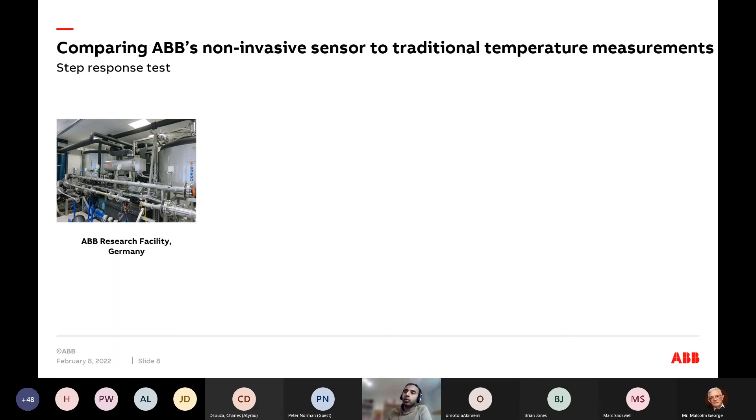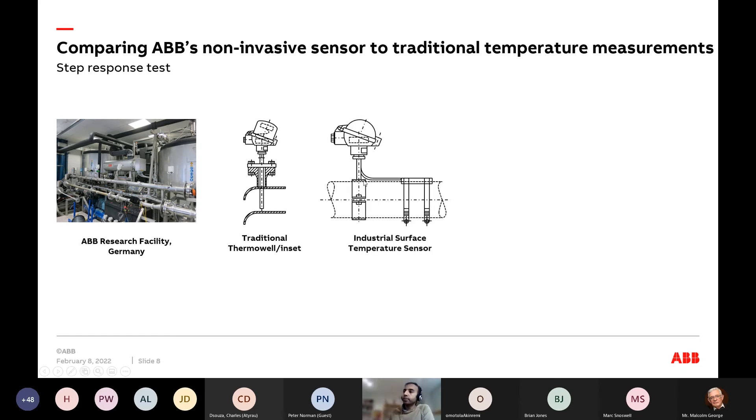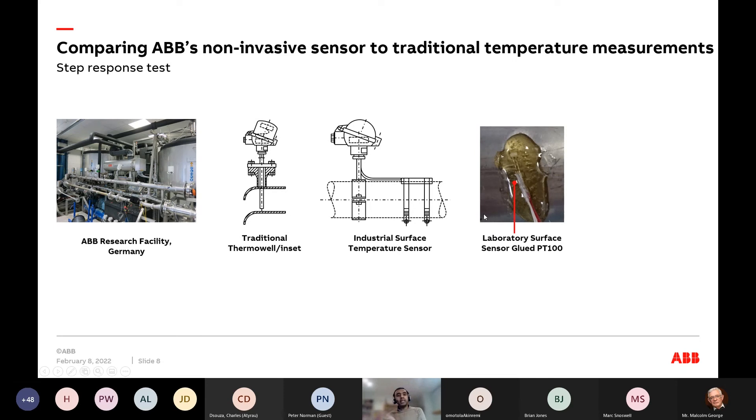Let me show you how this physics plays out in real life. This is our research facility in Germany — two tanks where we heat up water and pump it from one tank to another through a metal pipe. We compare a traditional thermowell with a typical skin temperature sensor, and what we call a glued PT100 — where we literally glued the PT100 sensor right onto the pipe with an insulated backing. This is the closest measurement to the true temperature of the pipe wall.